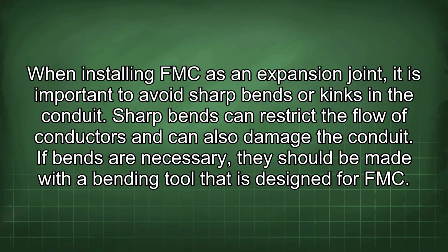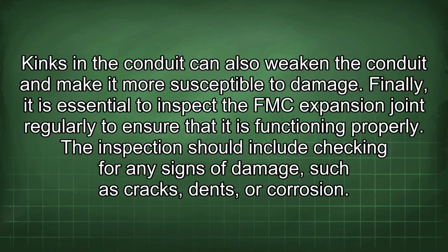When installing FMC as an expansion joint, it is important to avoid sharp bends or kinks in the conduit. Sharp bends can restrict the flow of conductors and can also damage the conduit. If bends are necessary, they should be made with a bending tool that is designed for FMC. Kinks in the conduit can also weaken the conduit and make it more susceptible to damage.